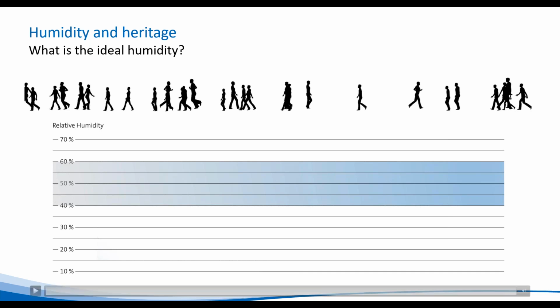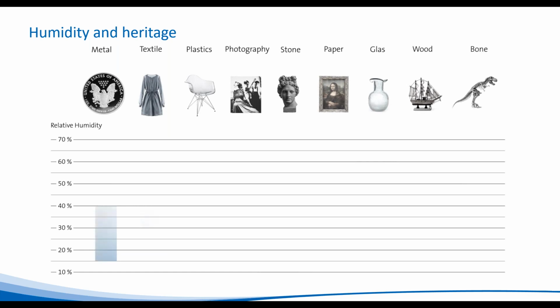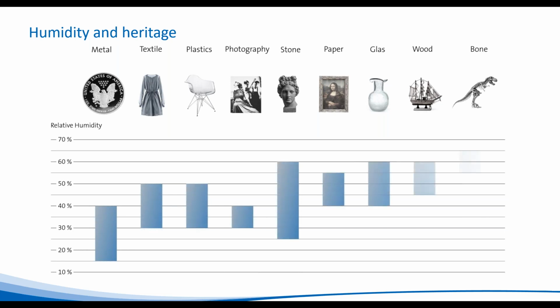But people are super important to a heritage environment, but also it's really important to consider the materials in the space. So a typical band of humidity control for artifact conservation is also 40 to 60%. But with a vast array of materials in question and all the different levels of moisture equilibrium that these materials have, the ideal humidity for conservation is very much material dependent, as we can see from this visual guide. So you'll see a lower moisture content requirement for metal, so we want to avoid corrosion. Textiles, we would typically maintain between 30 and 50% RH to maintain the inherent structure of the fabric. And plastics between 30 and 50%, especially when plastics are attached to other hygroscopic materials, such as chairs with wooden legs, for instance.